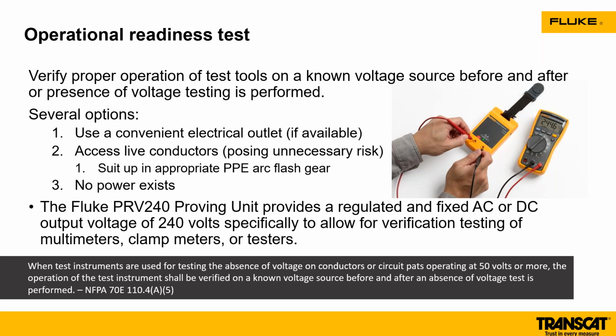Again, this is a great little tool. It uses batteries and simulates 240 volts for this one, and that way we can prove out that the meter was working correctly. Again, we can do this with AC or DC and give you that 240 volts. It's part of the 70E. As you can read down here at the bottom, it's part of the 110.4 standard, making sure that your instrument is tested for the absence of voltage and that it's working correctly. And that's really the key win.